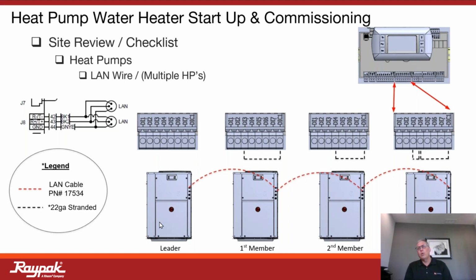Who's got the ball on this? Who's doing the wiring? And so this is essentially point-to-point wiring. We do offer a cable that simply plugs and connects from each unit, but then also each unit will have a jumper across it, as it's shown here. The leader on this particular terminal, as located below the display, there is a terminal block, and that terminal block for the first follower will have a jumper that looks like this. The second follower will look like this, and so on. And again, we can cascade up to 4 units. And again, multiple banks of 4 heat pumps is absolutely acceptable.